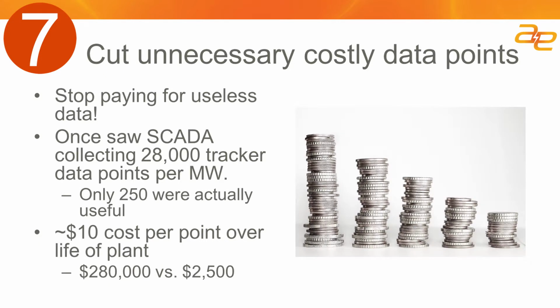The last issue I see with tracker systems in general is people tend to want to collect all the data they can and historize it. Various tracker systems from different manufacturers have a widely varied amount of data that can be collected. Towards the end of my career, on one site we counted and found 28,000 data points per megawatt just for tracker data. Of all those available points, only several hundred were useful, but taking all of them into a historian would have been prohibitively expensive.